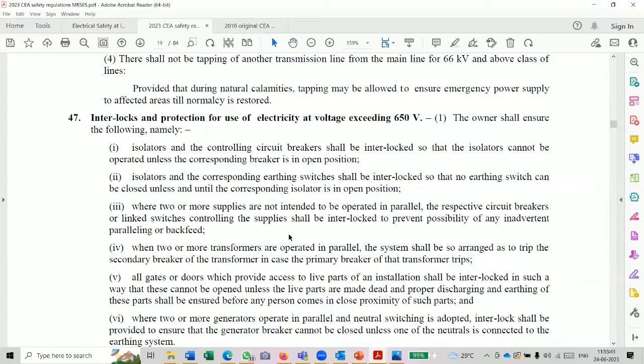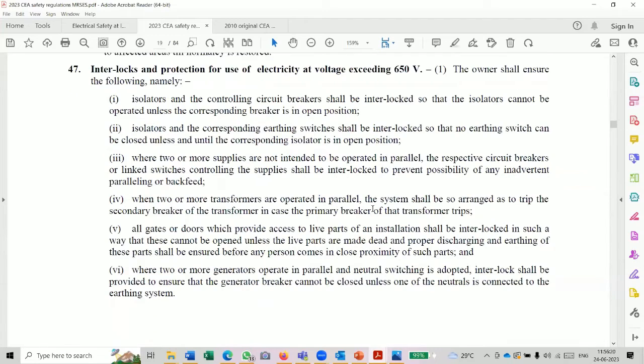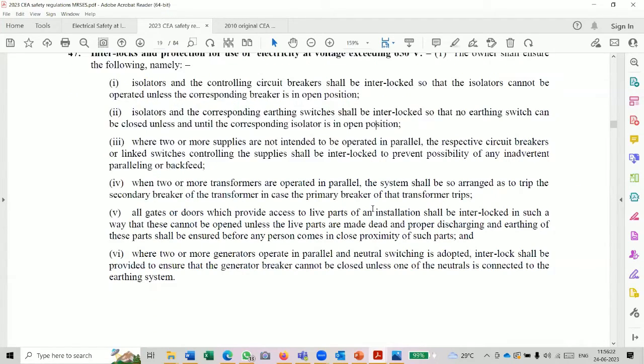Actually, the regulation title says at voltage exceeding 650, interlock and protection. That's the title. This gives complete confusion to the consumers as well as the inspectors. But they know that it is applicable for all. For example, see sub-regulation 1.3, which says an interlock should be provided for avoiding backfeeding. And see sub-regulation 2.4, it insists on an earth fault relay for 100 kV DG set.